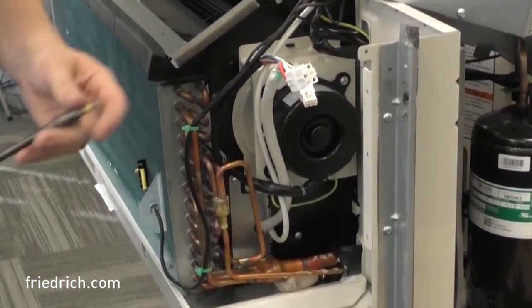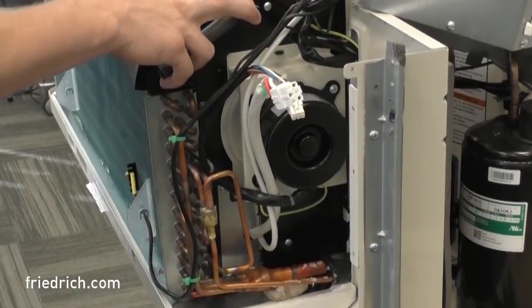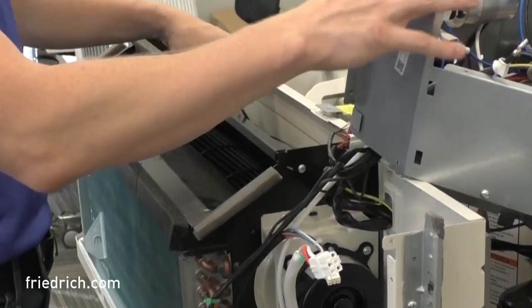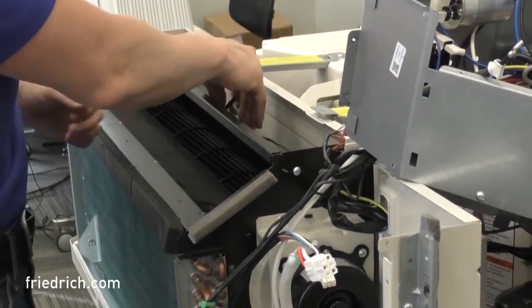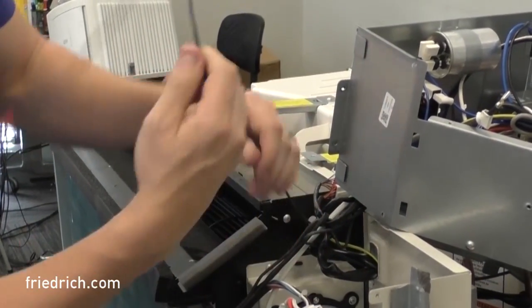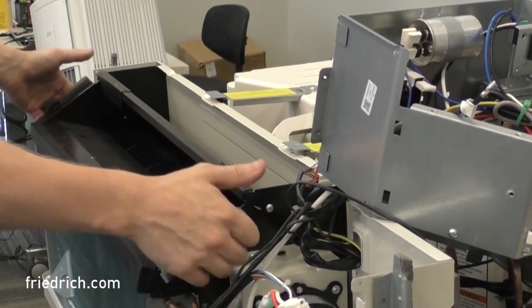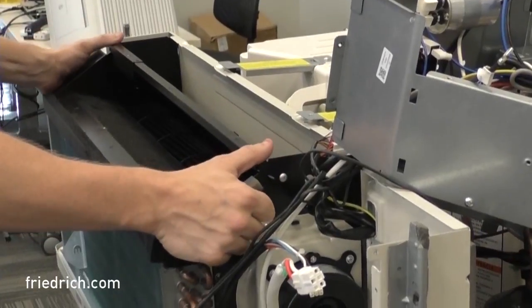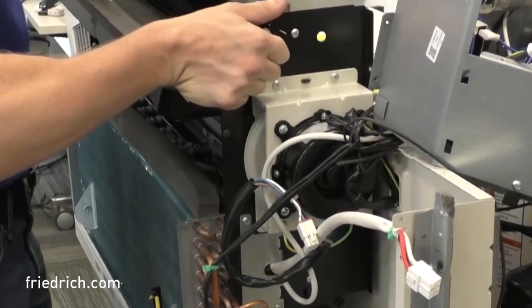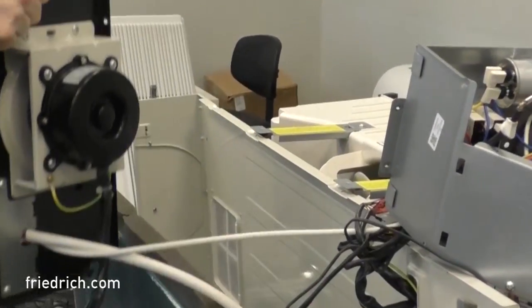Now I've got all four of those screws removed. The last thing I'm going to do before pulling this housing up and out is take the discharge air thermistor that goes into the housing but is still attached to my control box, and pull it out of its retaining clip — it just pulls straight to you and slides right out. Thread it through its hole and set that aside. Now I have everything disconnected. I can grasp the sides of the blower housing, tilt it towards me a little bit, lift straight up, and pull the whole blower housing straight up and out.